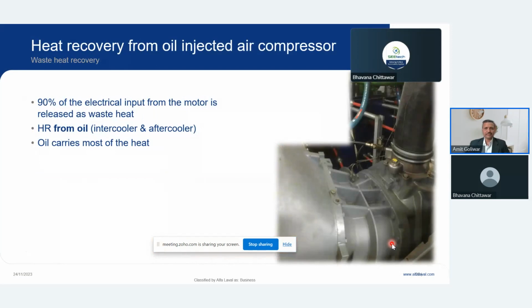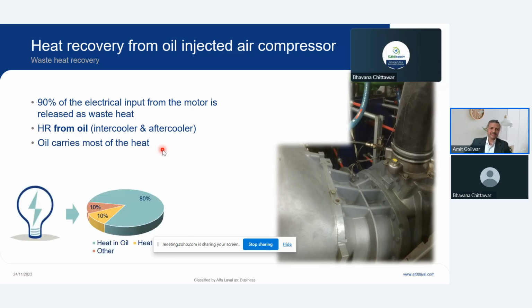After the cooling tower, we have compressors. Compressors work on electricity, and 90% of the electricity consumed for generating hot air basically goes into the oil. This is a compressor. The oil which goes inside will carry 80% of the heat. 10% of the heat will go into the air, and 10% will be dissipated in the parts of the compressor. So 90% of the heat is potential to recover.